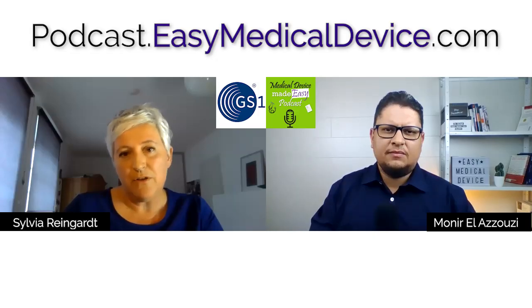The UDI-PI, production identifier, is a numeric or alphanumeric code that identifies the unique unit of device production. There are different types of UDI-PIs, for instance serial number, lot number, software identification, manufacturing and or expiry date. If you're working with GS1 standards, there's another concept called the application identifier concept, which allows you to encode that information in a structured way within a GS1 barcode. And the combination of both is the UDI code.